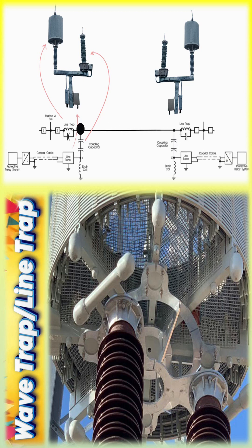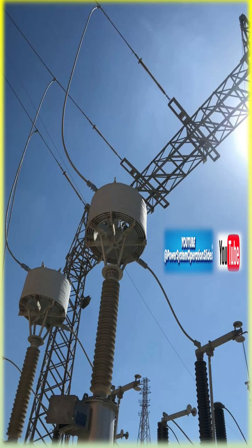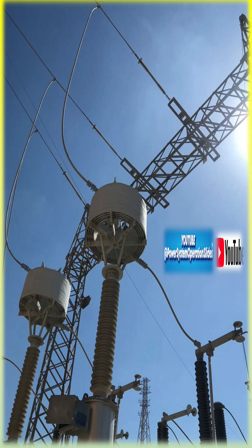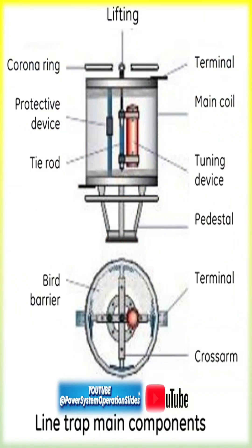In high-voltage transmission lines, apart from the usual 50 or 60 Hz power frequencies, high-frequency signals ranging from 30 kHz to 500 kHz are superimposed onto the power lines. These high-frequency signals are used for various purposes, such as teleprotection, remote control, data transmission, and relaying information between substations.